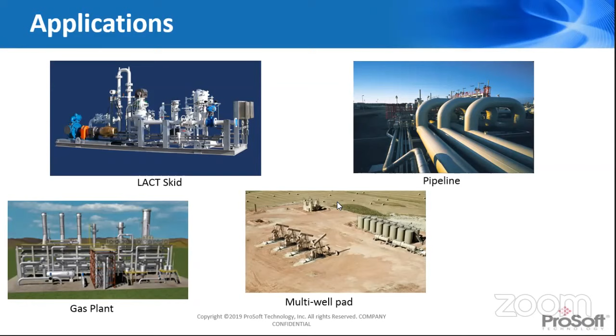So this is a sample of something for a LACT skid where you can use the L24 or L27. You can use anything from gateways or Modbus communications to things like a Coriolis meter on that skid. A lot of the Coriolis meters are also starting to build in EtherNet/IP, so you can bring that information directly into the controller, things like pulse count or pulse frequency, as well as density.